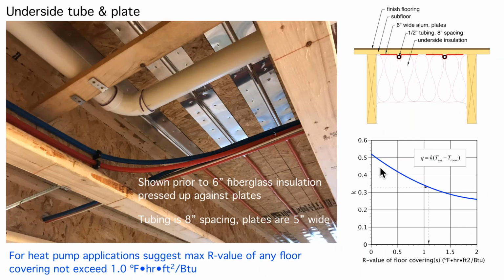Here's a photo. We're looking up at the underside, and this is what's called a below floor tube and plate or underside tube and plate system. You can see the aluminum plates here that have been stapled up tight against the subfloor. You'll see a gap right in here, and then there's some more plates. The reason there's a gap right here is that it's directly under a kitchen island, and there's no point in adding heat to a floor that has cupboards or cabinets directly above it. In fact, if you store food in those cabinets, that heat is not good for the food. It'll cause premature spoilage of the food.